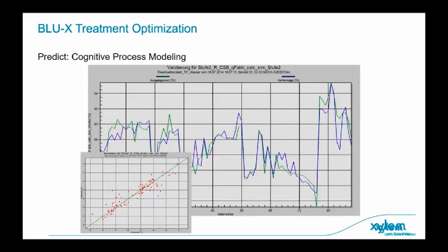What is very key for anything like this is that there's extensive QA/QC on that data. So any issues related to sensors, including drift, missing data, spurious data, will be flagged immediately to operators to ensure that the operation isn't being carried out on faulty or missing data. And there will be very clear fallback operational strategies that can be put in place to make sure that it's never going to go rogue. That's extremely key with this kind of platform.